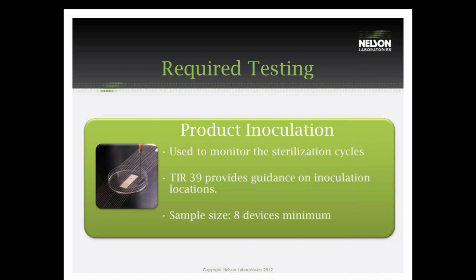Following the bioburden testing, we will take eight devices for a one cubic meter load and evaluate the devices, looking for the hardest-to-kill location. TIR-39 provides guidance on what type of inoculation locations to look for. Those include small lumens, mated surfaces — anything that's going to present a challenge for EO to penetrate. We will then inoculate the devices in as many locations as needed. Some devices may have three to four inoculation locations for a complex device, or just one depending on how difficult the product is to sterilize.